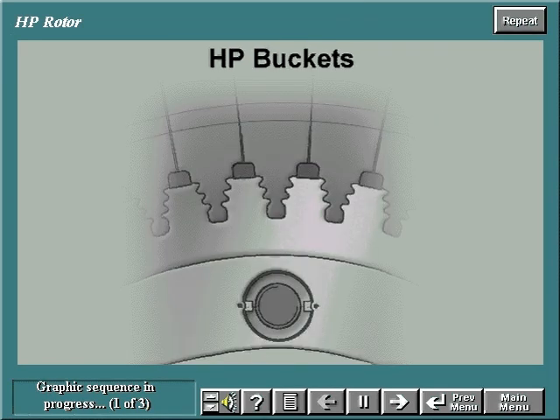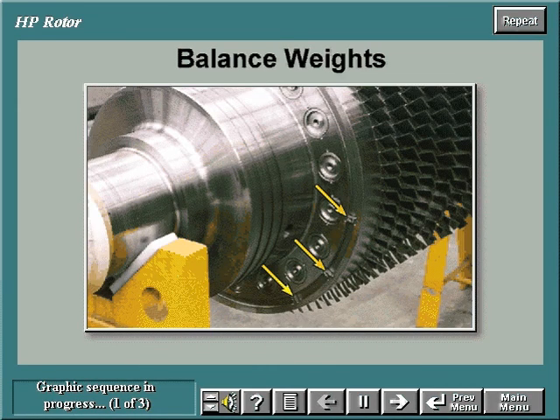The buckets are now assembled in the dovetail slots of each high pressure turbine wheel. After the buckets are installed, locking plates are inserted between each pair of buckets and the wheel rim to tighten the dovetail fits. Each locking plate has a tab that must be bent and broken off using sufficient axial force to ensure that the locking plate makes full contact with the buckets. Once the high pressure rotor is completely assembled, it is slow speed balanced. Balance weights are inserted and staked in place to make sure vibration levels meet design standards.